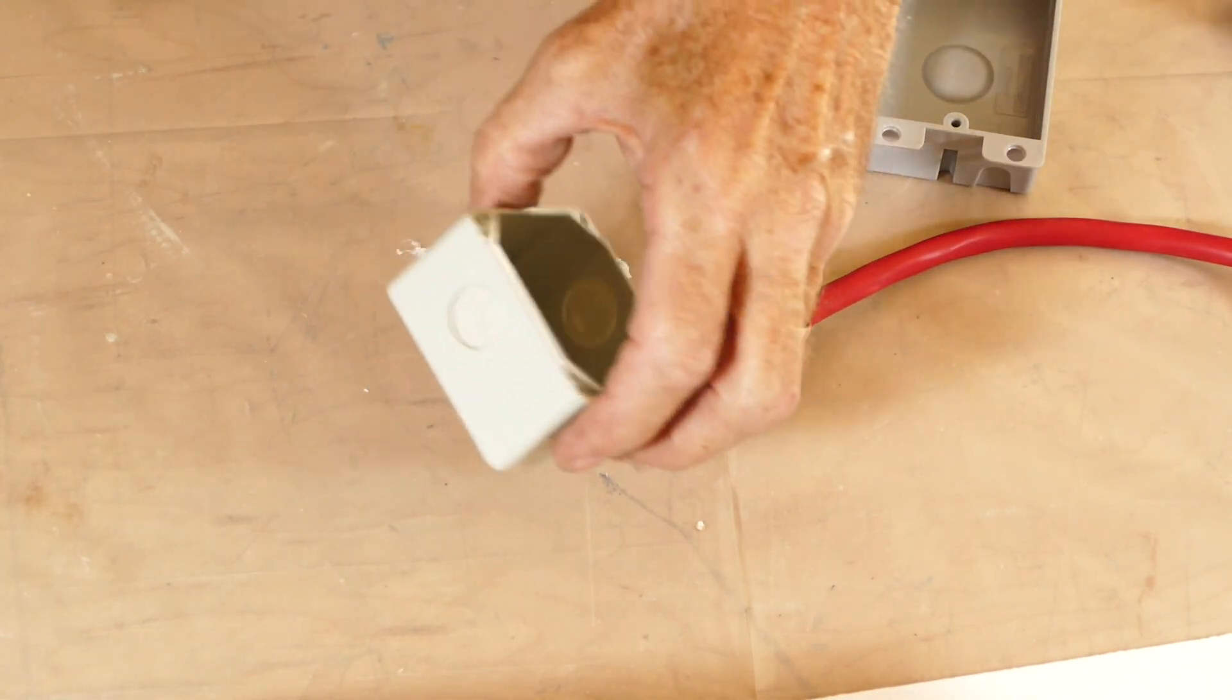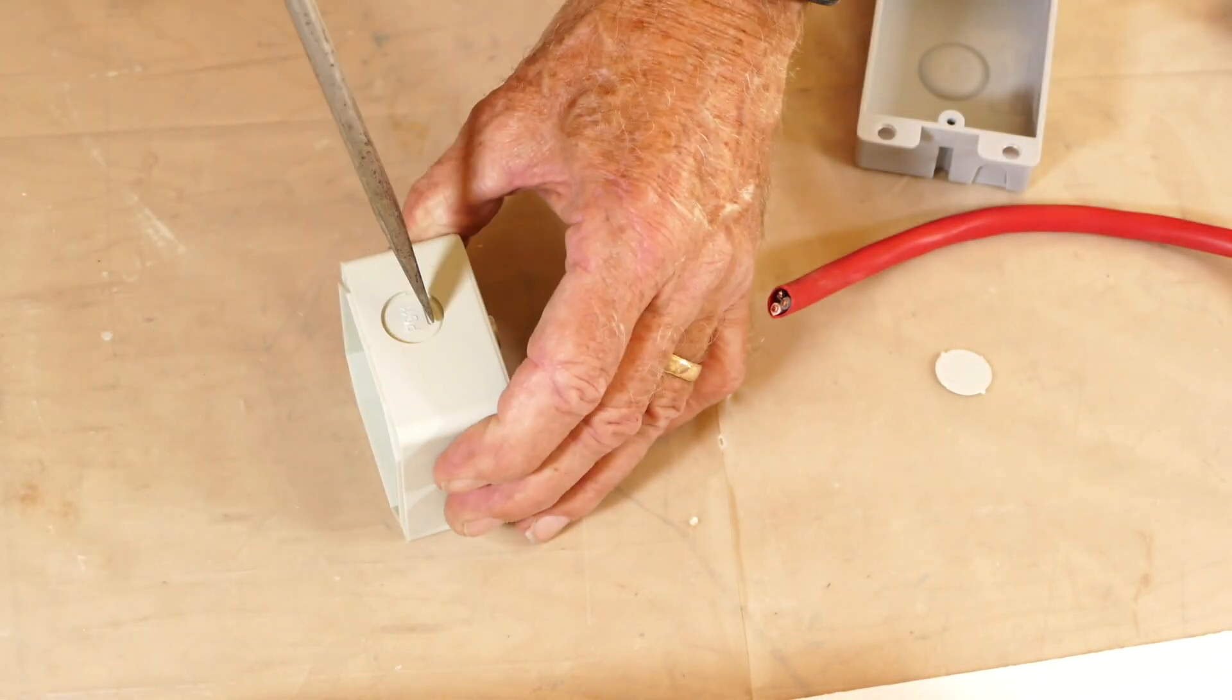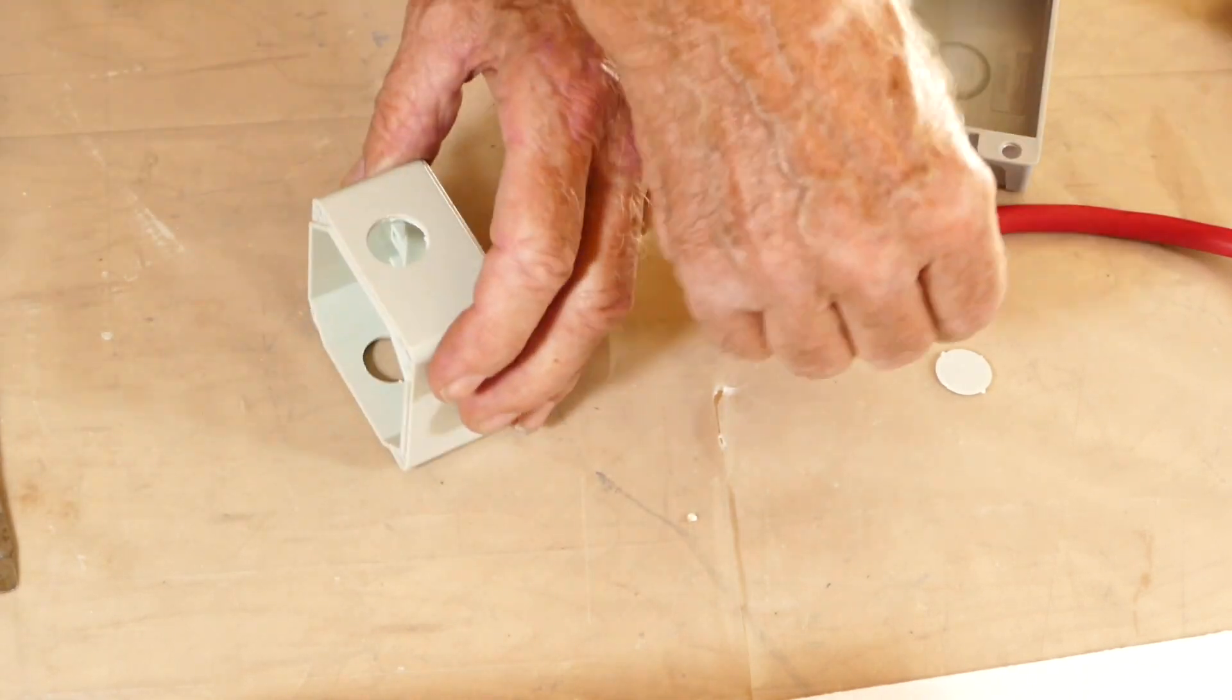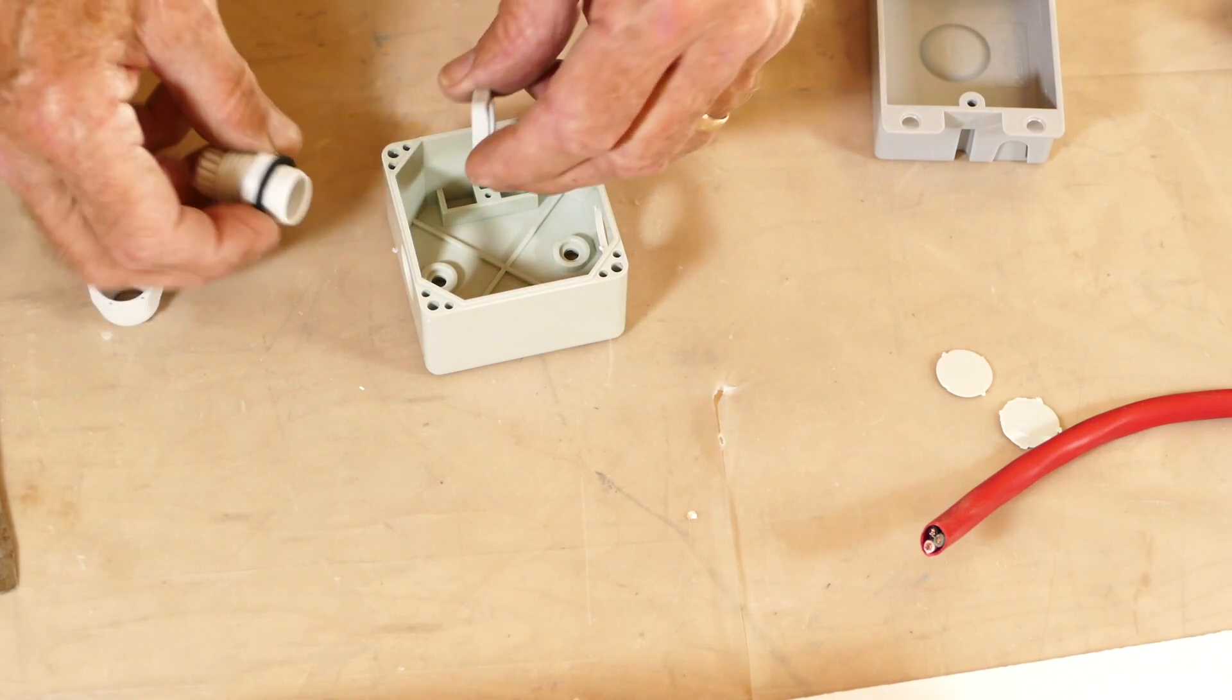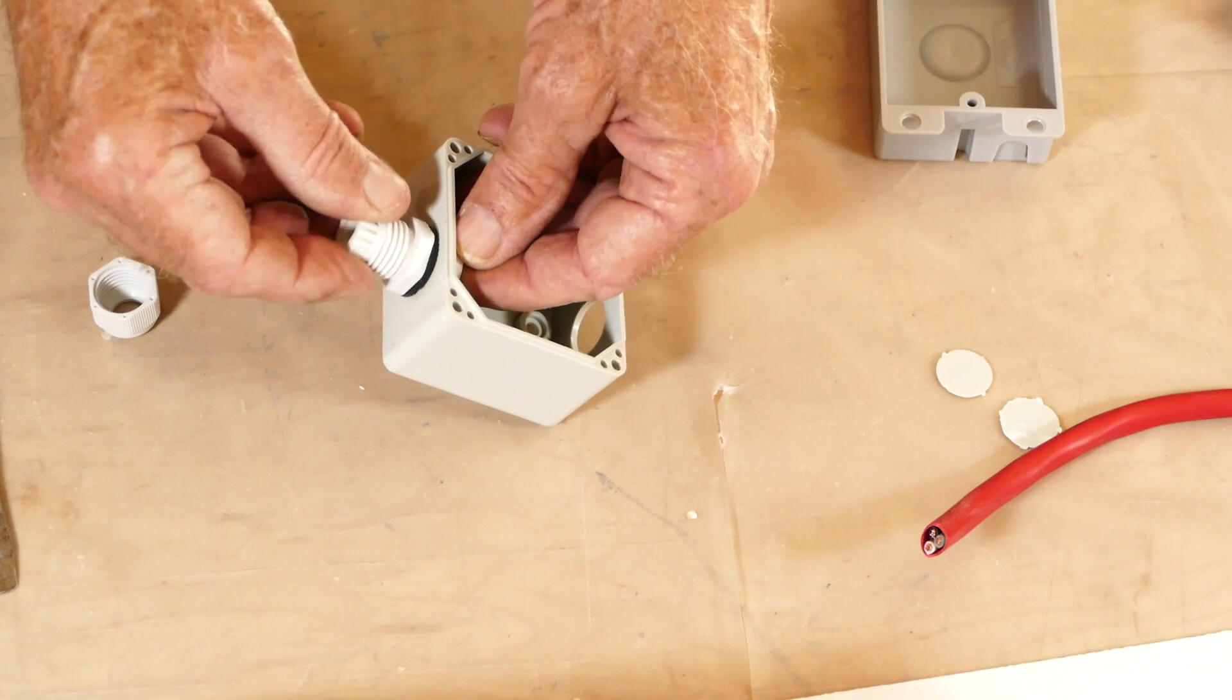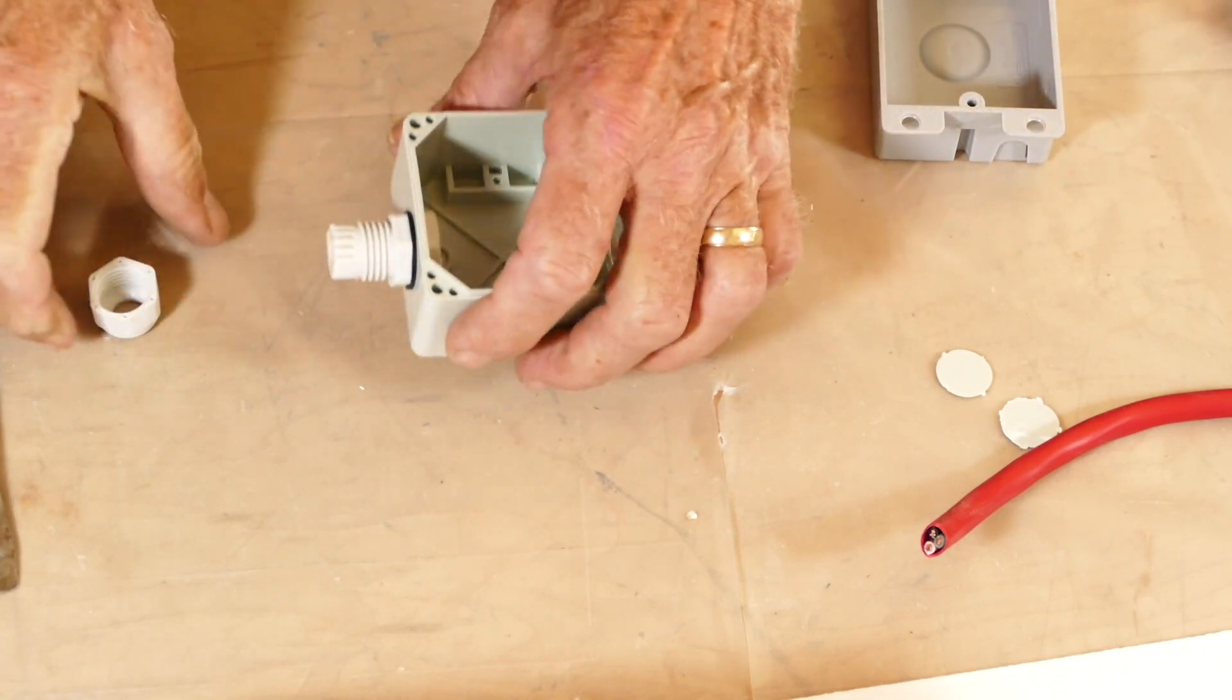The switch enclosure has two punch outs or knock outs that are used for routing the three cables. Use a screwdriver to remove them. The switch comes with two cable glands that hold the cables in place and seal the box from moisture and bugs. Remove the nut, slide the gland into place, and screw the nut back on to secure the gland.